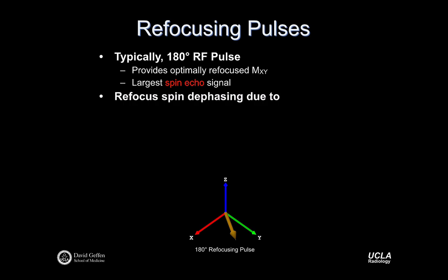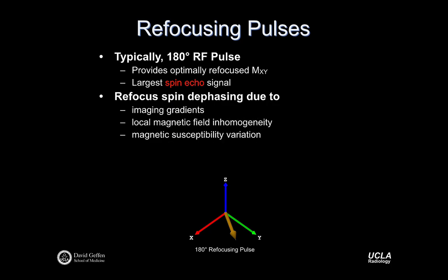This concept of refocusing: we've mostly talked about spins being on resonance, as if they're all going to precess at the B0 Larmor frequency, when in fact that's not exactly the case. B0 is not perfect, there are chemical shielding effects from fat and other things, and so there's a milieu of resonance frequencies. If something is not perfectly on resonance, we refer to it as being off resonance. If a spin is off resonance, it will tend to dephase. It will accumulate a phase relative to the on-resonance spins because it has a slightly different precessional frequency, so those spins drift apart from each other in precessional phase.